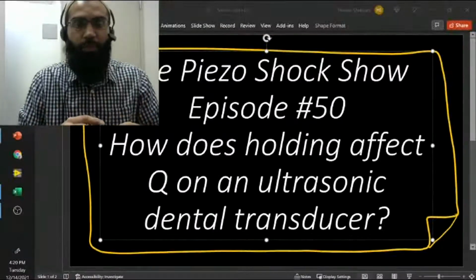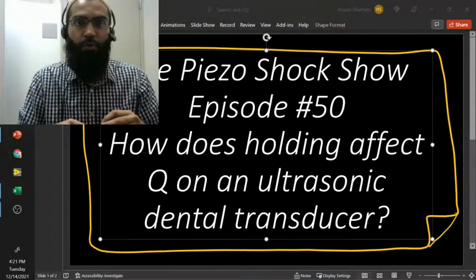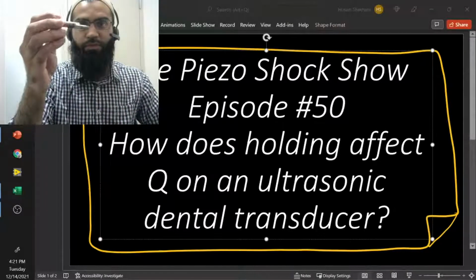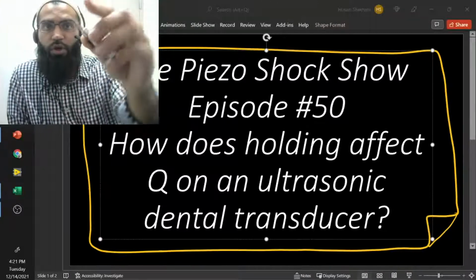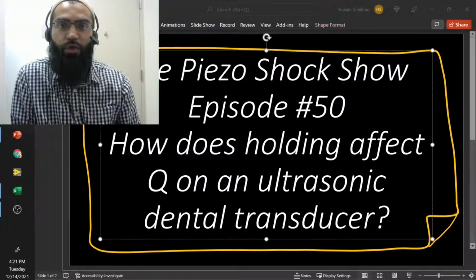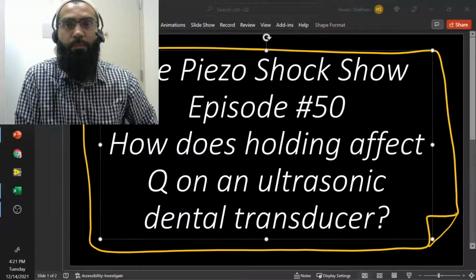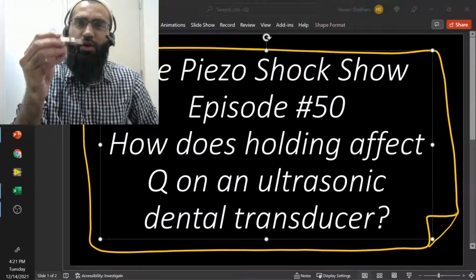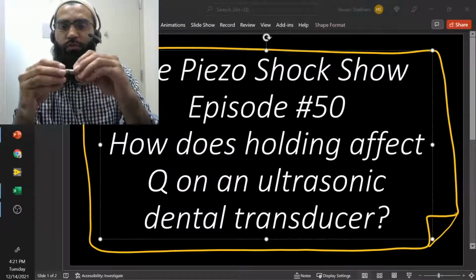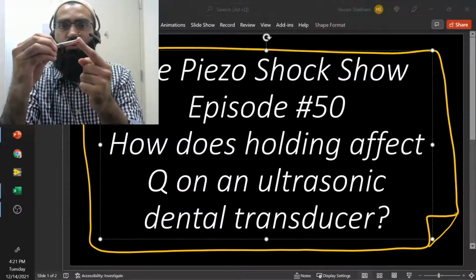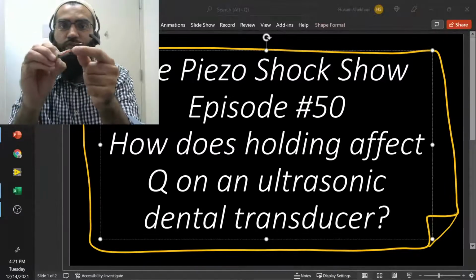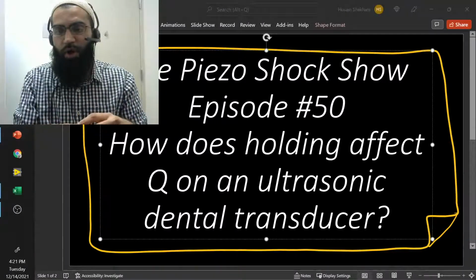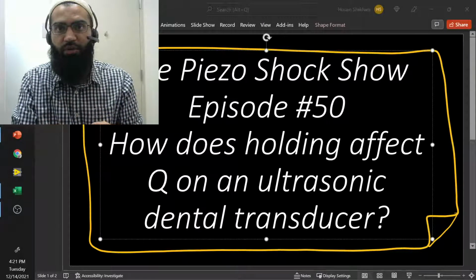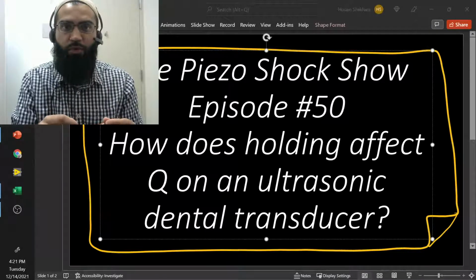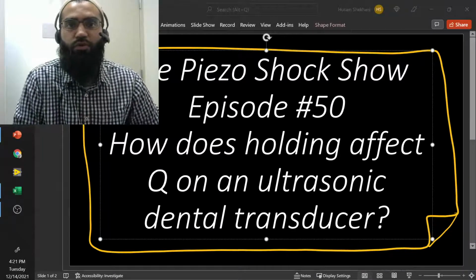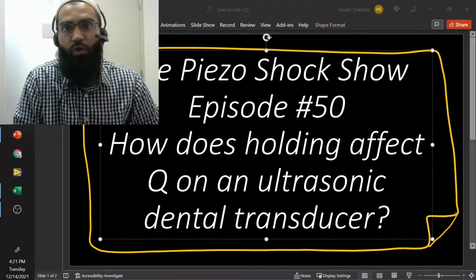All right, we are back. We are on episode number 50, and we're going to keep discussing the dental transducer that I showed you in the last episode. Today, we're going to be doing some impedance measurements, seeing how that holding mechanism of putting an O-ring at the front and pushing back against the transducer on the soft pad actually ends up affecting the performance. Now, there's two methods that we use to determine how holding affects performance.